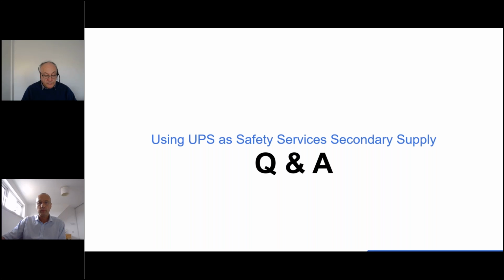Thank you. Somebody else has asked, how many travels of a fire lift are required in battery run time? Well, that's unfortunately down to the designers. If it's an evacuation lift, it's how many times it takes to evacuate that building. If it's a firefighting lift, that can be used at any time and all the time during an emergency situation, so that would have to be sized for constant use for the constant time. So different lifts, different applications.